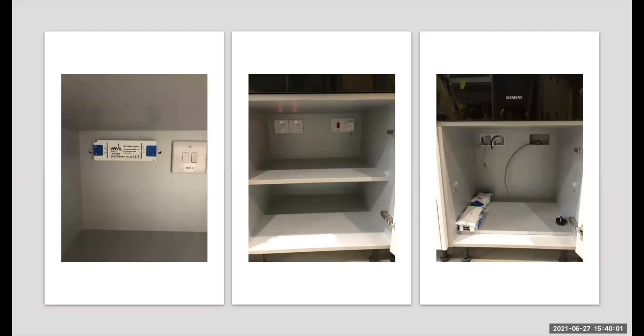And then when you enter the cupboards, I mean, these had solid backs to them. These were 18 mil solid backs. So fast fix boxes fitted beautifully on these. If not, what I have done before is I've mounted a piece of stud to the wall and then put in metal knockout boxes and secured my boxes to those, my accessories to those. As you can see, it looks quite nice.